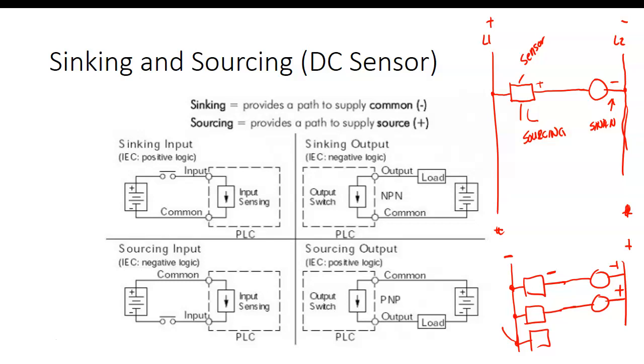So whether you understand it or not, the problem is they don't call these sinking sensors, and they don't call them sourcing sensors. They have what we call PNP sensors. These are sourcing sensors. And then we have NPN. Guess what these are? So you need to understand your system, because if you go out and you want a metal detector and buy the wrong one, you're going to try to troubleshoot something else.